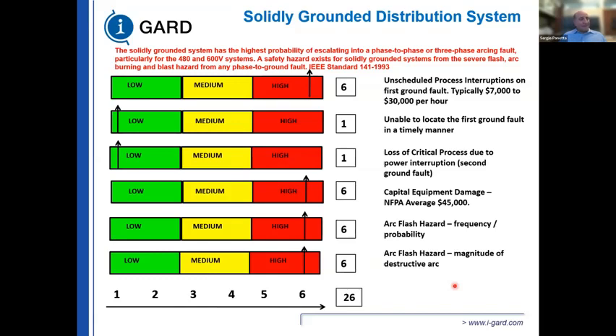Capital equipment is fairly high because you still have to replace a piece of equipment due to a ground fault, because you have 40,000 amps of current flowing at that piece of equipment that is faulted. So if it was an air conditioning unit, you probably have to replace some portions of the electrical equipment. If it was a large motor that was faulted, you have to replace that large motor. The arc flash hazard is high, and the frequency is high, and the magnitude is high. So now we're at 26.